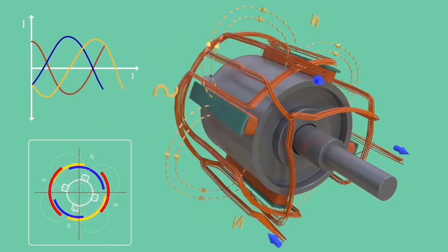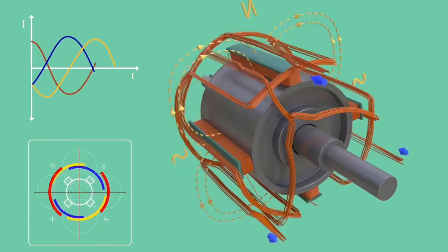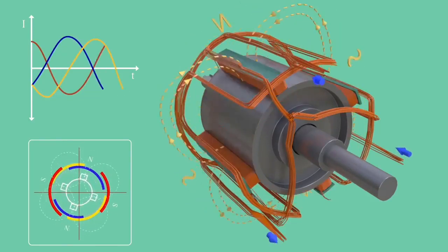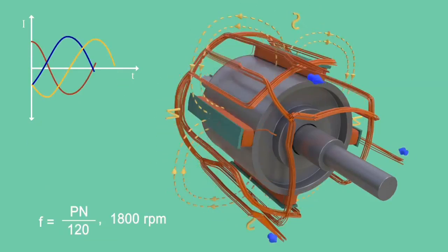It is clear from the equation above that in order to produce 60 Hertz electricity, a four-pole rotor should run at a speed of 1800 rpm. Such huge rpm will induce a tremendous centrifugal force on poles of the rotor, and it may fail mechanically over time.